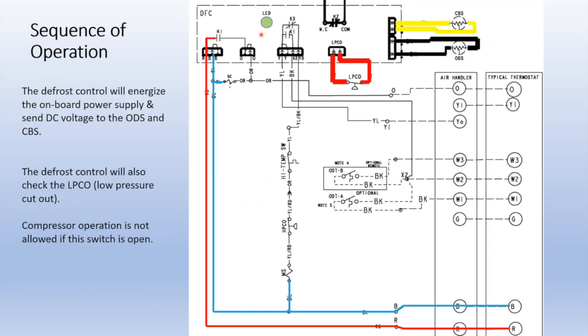Once it's powered up, the board is going to create 3.3 volts DC, and it's going to put that through the LPCO, and it's going to verify that's closed. It's also going to put 3.3 volts DC into the two thermistors, the coil base sensor and the outdoor sensor. And then depending on what voltage it sees come back is what temperatures it's reading.